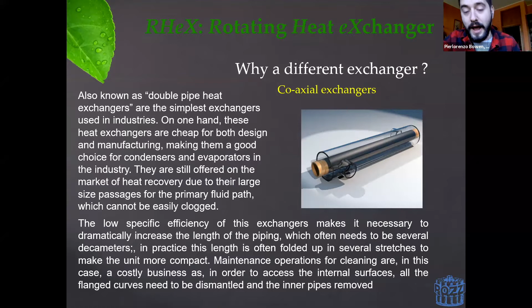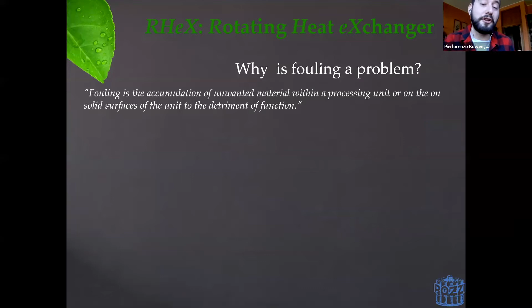Now, what is fouling and why is it a problem? Fouling is defined as the accumulation of unwanted material on the surfaces of a unit. In the case of heat exchangers, you can already imagine why this is a problem, because you're effectively putting an extra layer of material on top of your exchanging surface. And this material does not have the same properties as the metal that you're using for heat transfer.